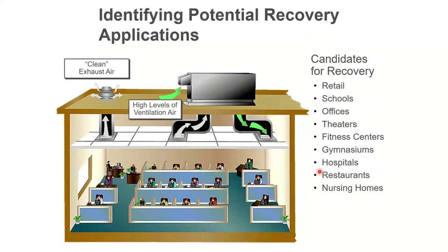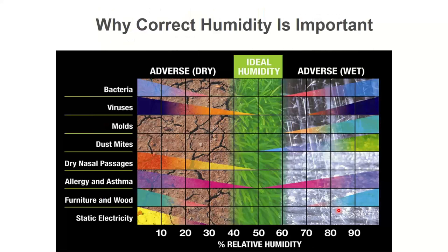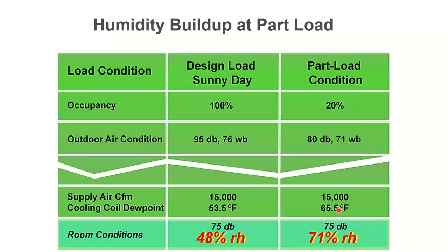The best candidates are ones that have a lot of outside air. Who's that? Offices, schools, theaters, fitness centers. These all have something in common, which is typically a lot of people in a relatively tight density. So those are the kinds of places where I'm going to be looking at putting an ERV in. It helps out with the humidity. If I can pre-humidify or pre-dehumidify the air, that's going to help us with the same discussion we just had about not having things too dry or too moist on that psychrometric chart. Keep things in that 30 to 60, 40 to 60 type range.